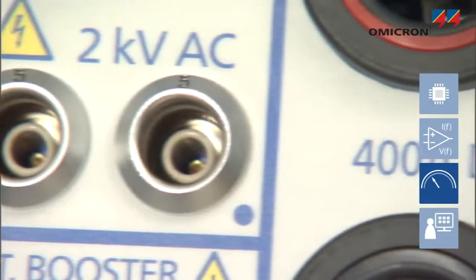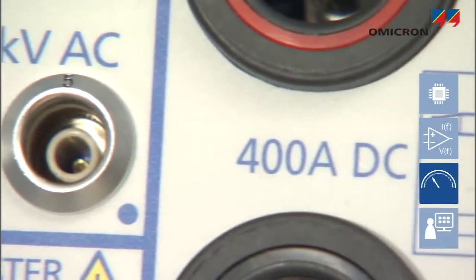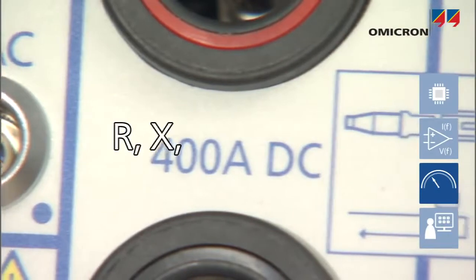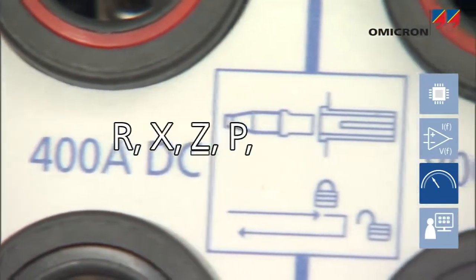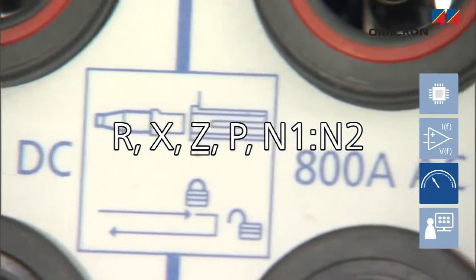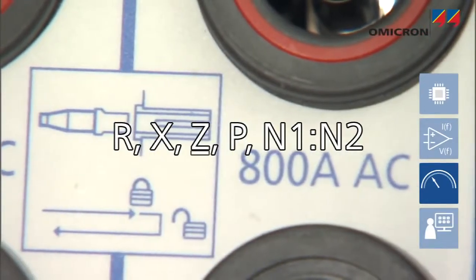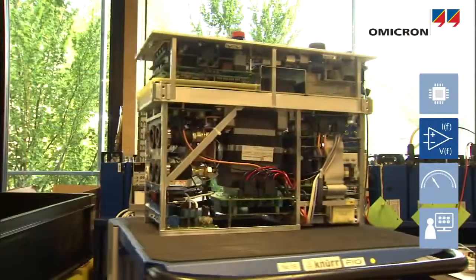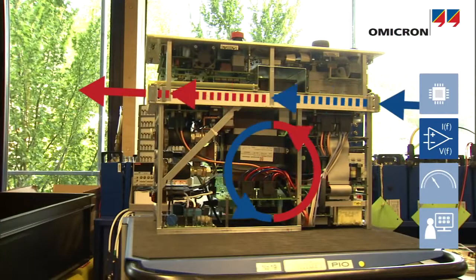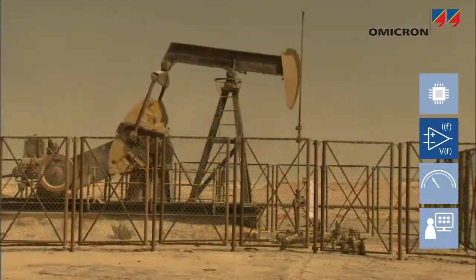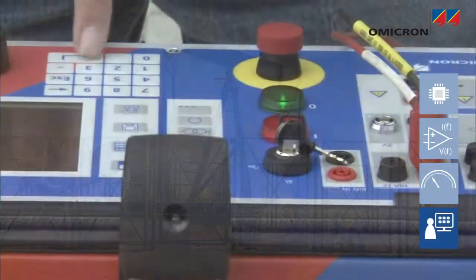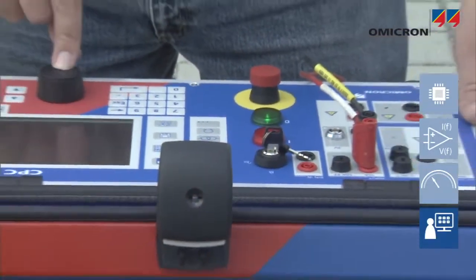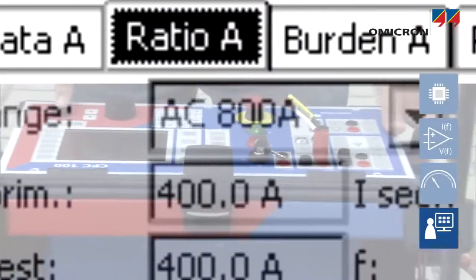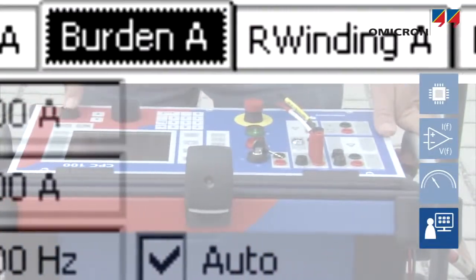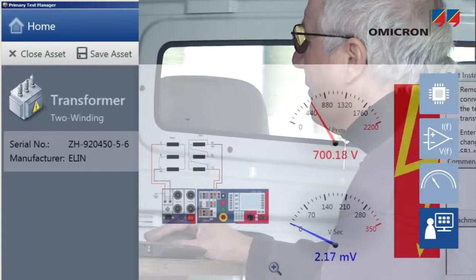Measuring input and output values in amplitude and phase allows one to determine resistance, reactance, impedance, power values, and electrical parameters such as ratio, polarity, or burden. Separate cooling channels make the device usable in wet or sandy conditions. The CPC can either be operated manually or by using its built-in testing know-how, either directly from the front panel or by remote control from a laptop.